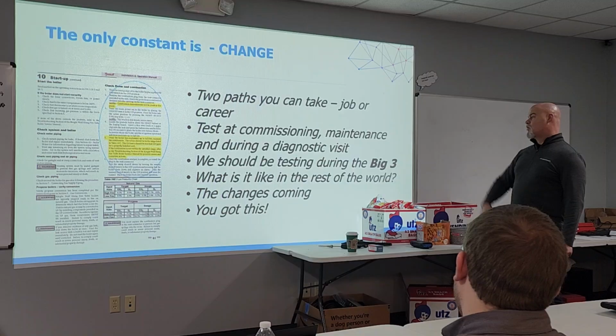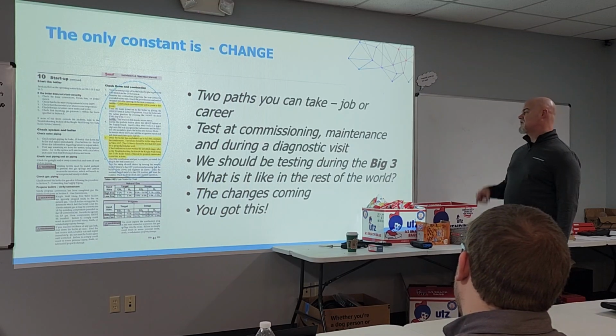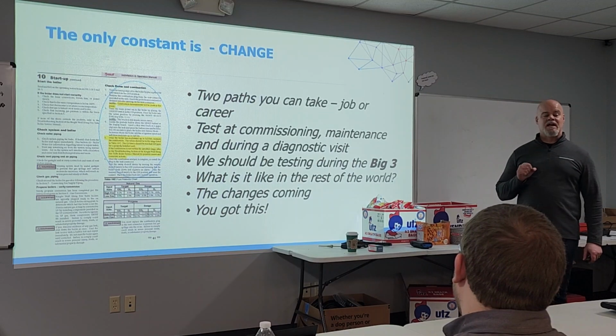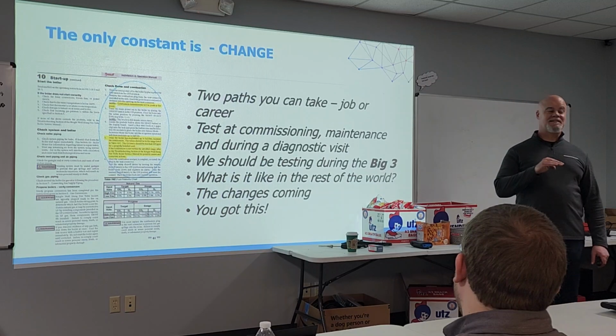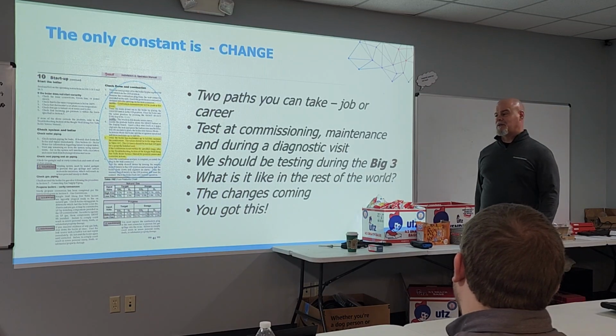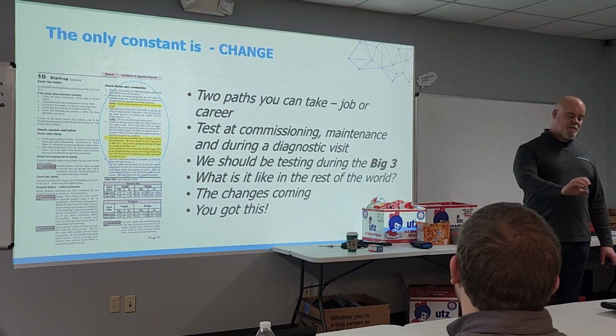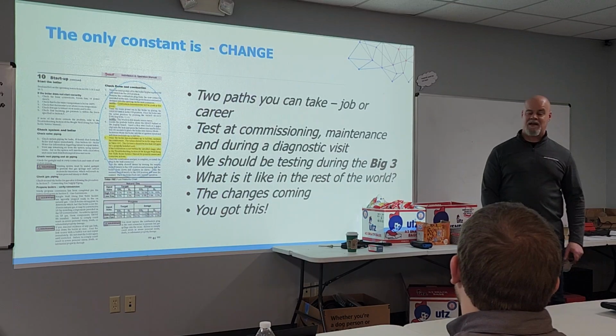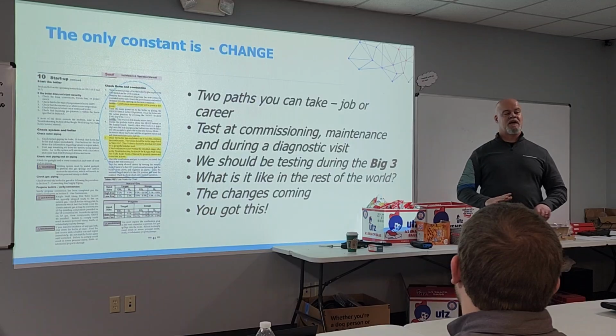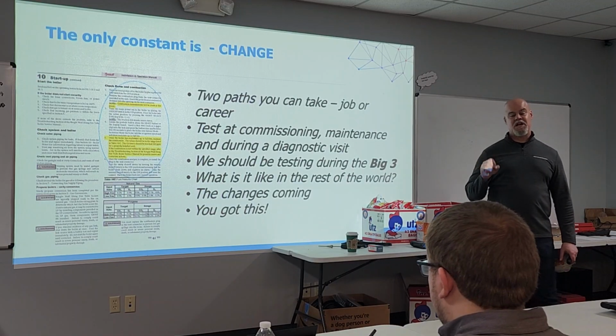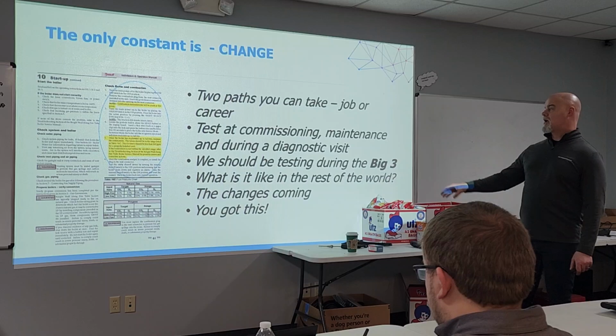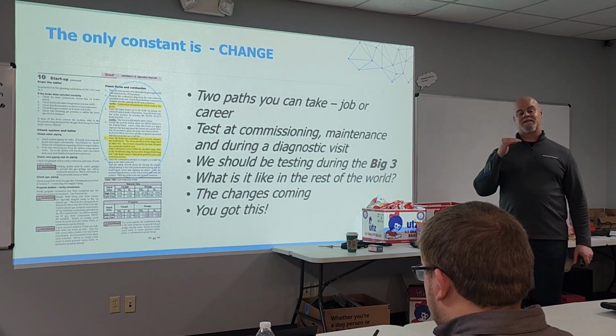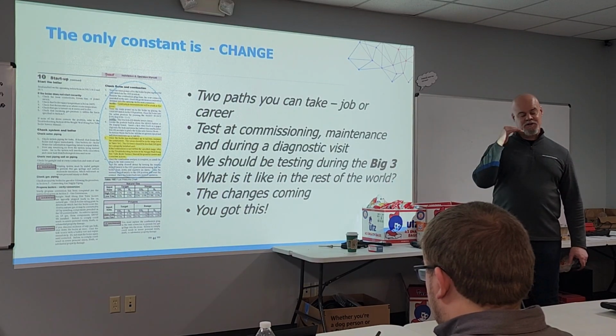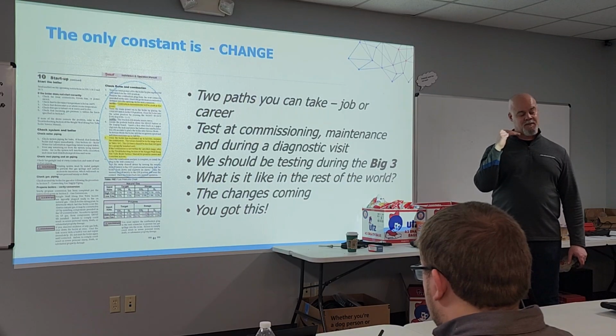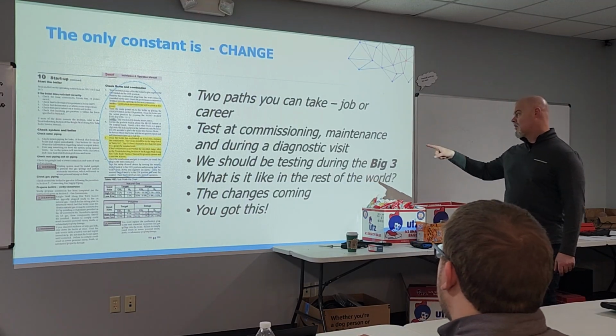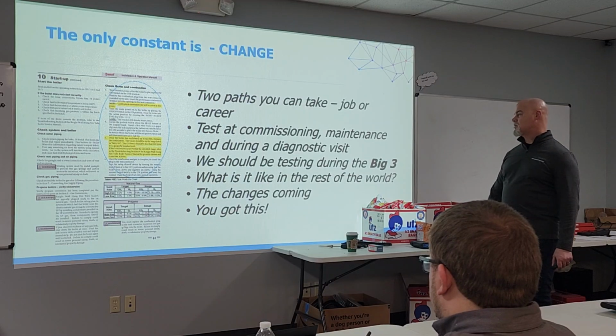We should be testing at commissioning, maintenance, and during a diagnostic visit. We have a nasty habit of thinking everything we install is plug and play. I'm here to tell you, this is no longer a push-pull, pick things up and put them down trade. It is the opposite, it is becoming a thinking person's trade. Things are changing, and changing rapidly, so we need to make sure we're thinking. Part of that is testing during different firing rates and fine-tuning systems, because the tolerances are becoming very tight. I'll cover the relevancy of commissioning, maintenance, and diagnostics later in the presentation.